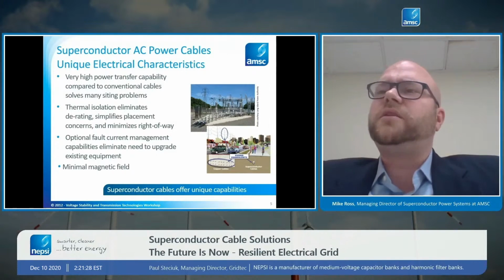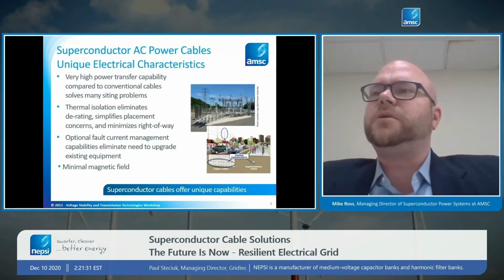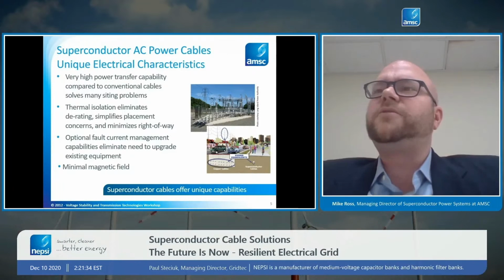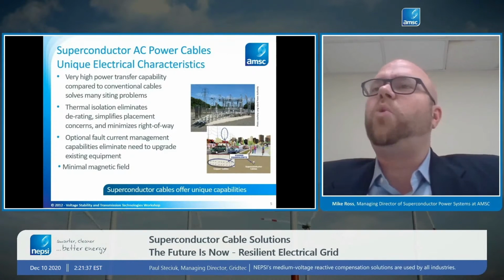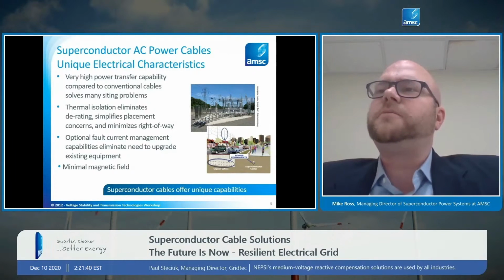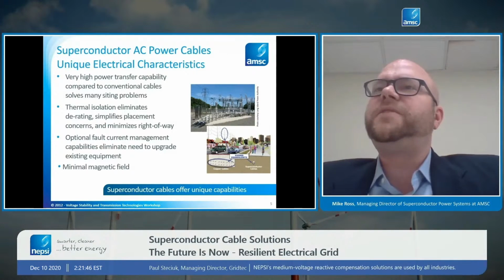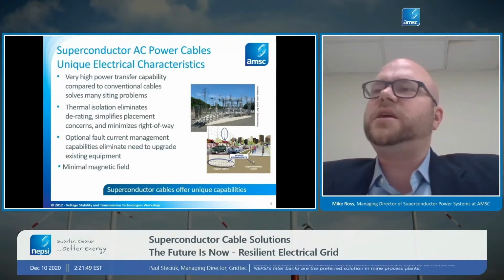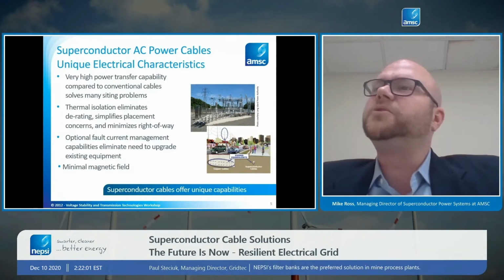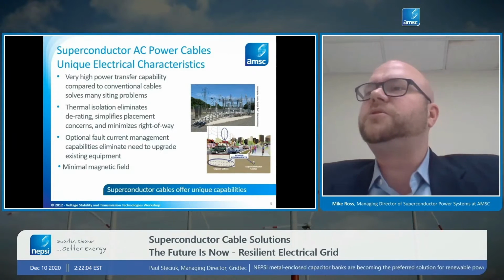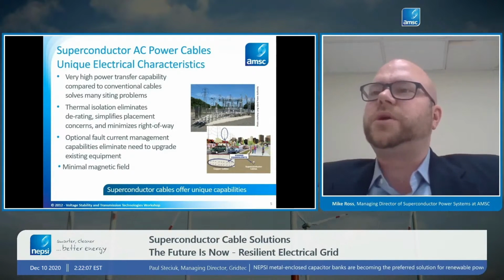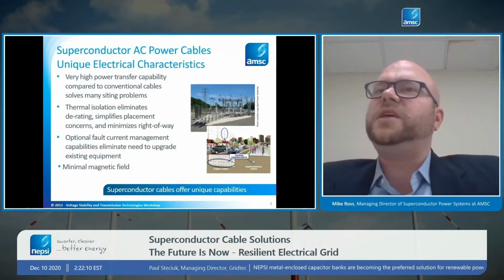Additionally, when you install a conventional copper or aluminum cable in a utility grid, there's a lot of requirements associated with getting the heat away from those cables. Anytime you run electricity through any copper or aluminum device, it's going to generate heat. And if that heat's not able to dissipate, eventually the device will break down and fail. So there's a lot of effort when utilities are installing power cables to make sure that heat dissipation is sorted out. You can't bury the cables too deep underground. You can't put cables too close to each other. All sorts of rules and requirements are needed in order to avoid this heat issue.